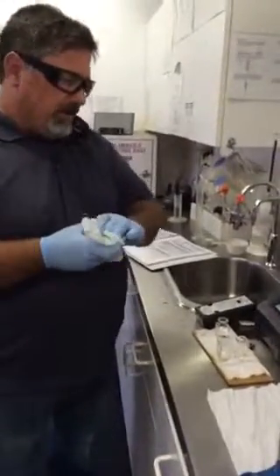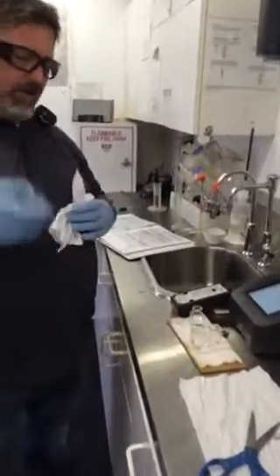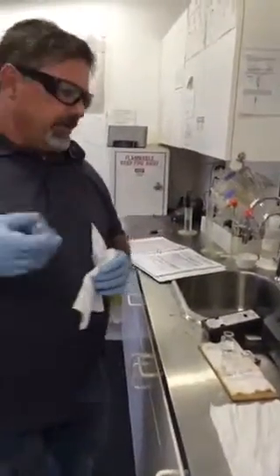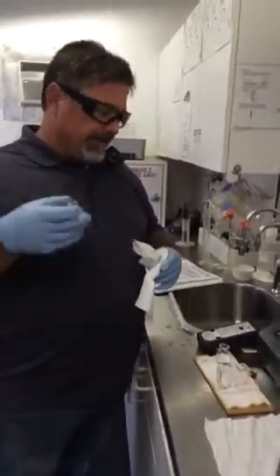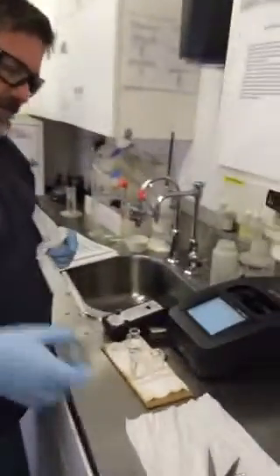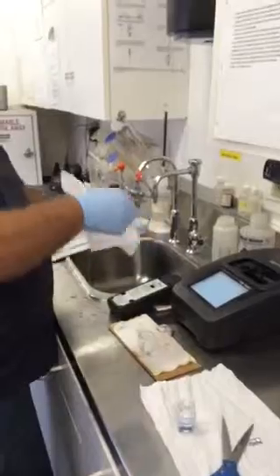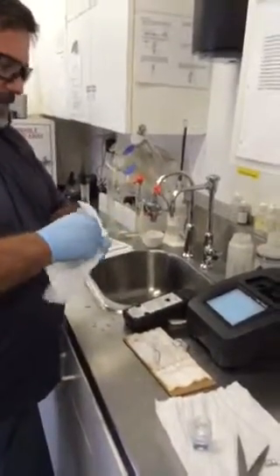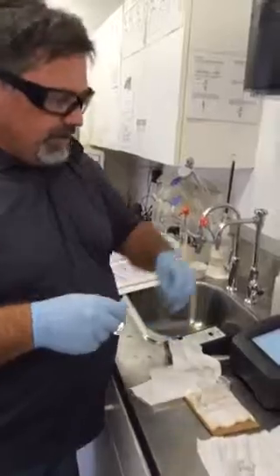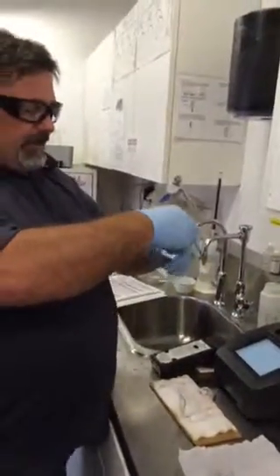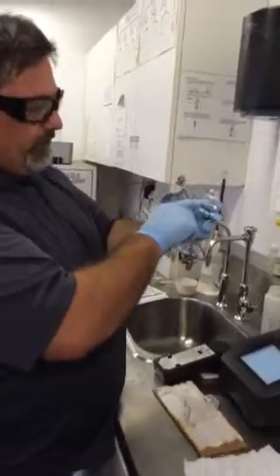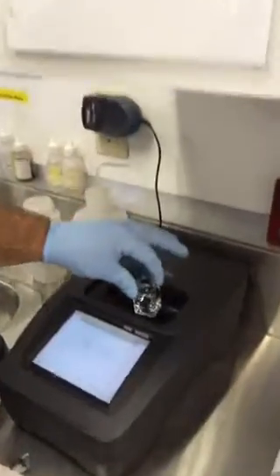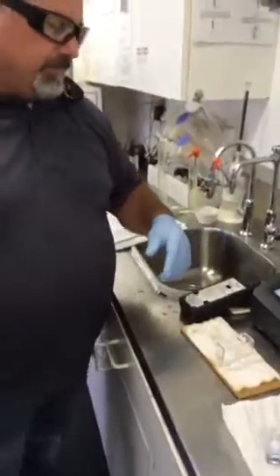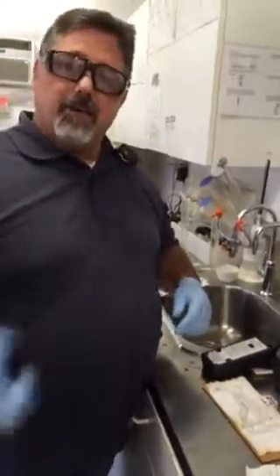So we want to make sure that we always clean our glassware before we take a reading. Anything on the outside could affect the final reading. Okay. So we're down to 110. So I know that's been about 30 seconds. So now I'm gonna clean this off, and I'm gonna just put it in. That way I'm ready for my 0. And always make sure that the little number, the writing, which is 10 ml at the line, has to be facing to the right as you put it in the DR2800, okay? So we're going to close that, and then we're going to pause for a second and come back when we get down to 0.